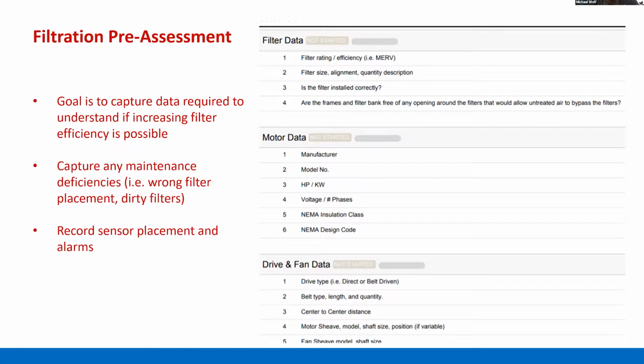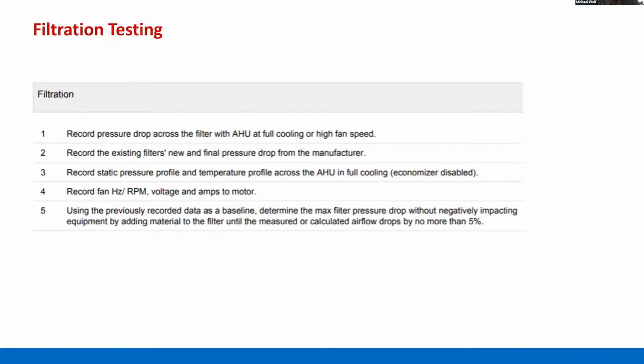The next slide shows a filtration functional performance test, where we're looking at what values we want, again, that commissioning tech or junior level engineer to record. Again, I highly recommend, if you can, utilizing a test and balance contractor to get some of these motor amperages, so you start to know the capacities and the limits of your system, and maybe what filtration efficiencies you can increase to in these air handling units. It is very useful information.